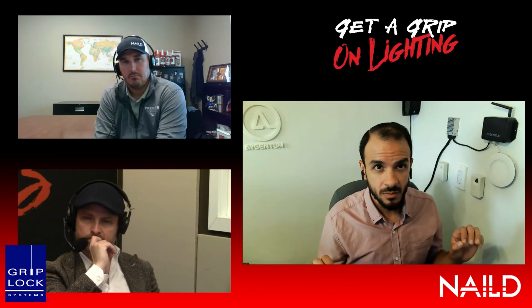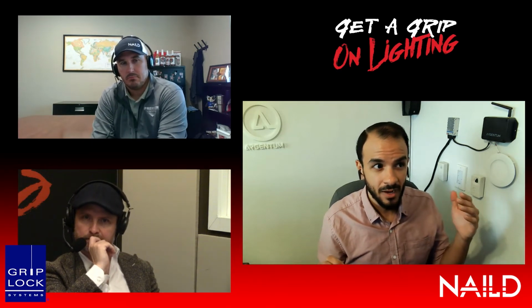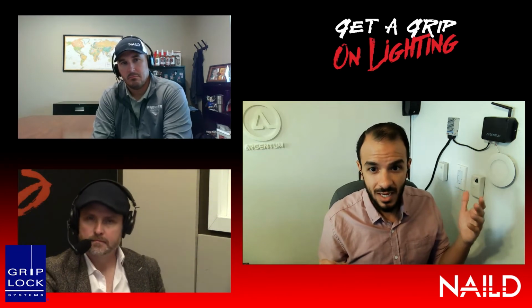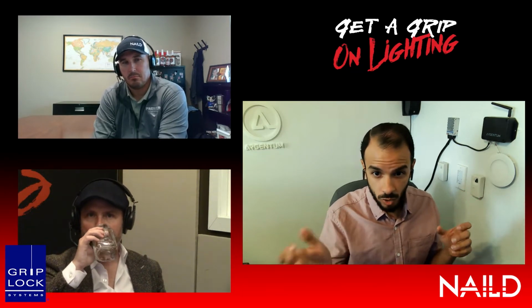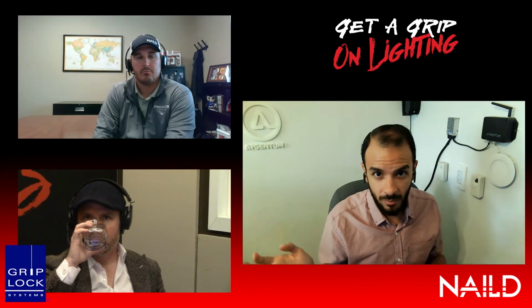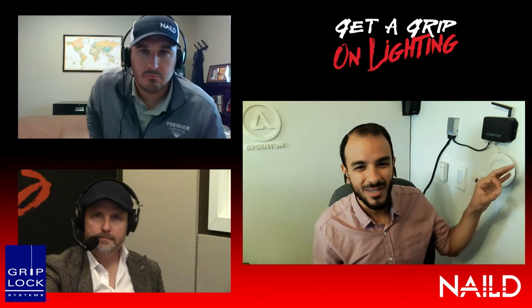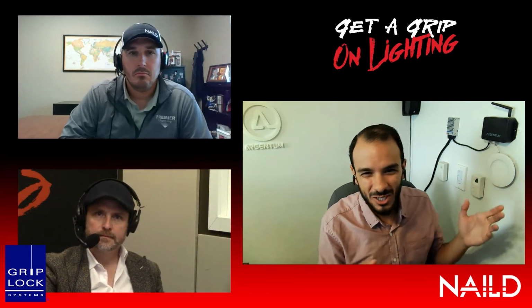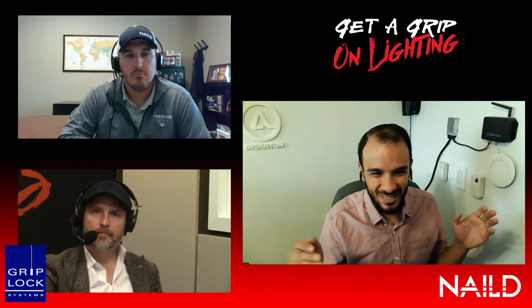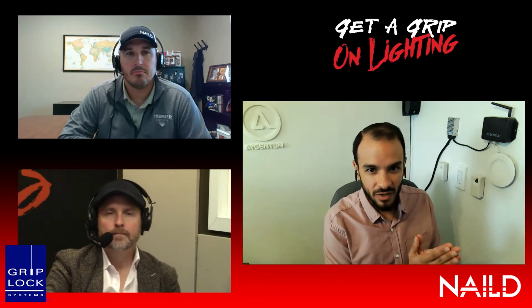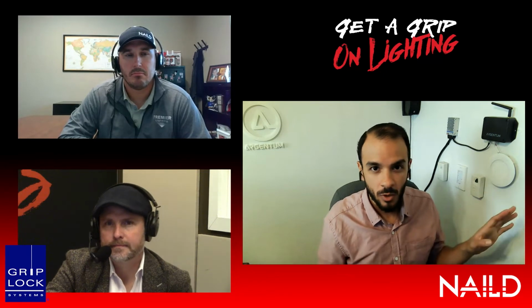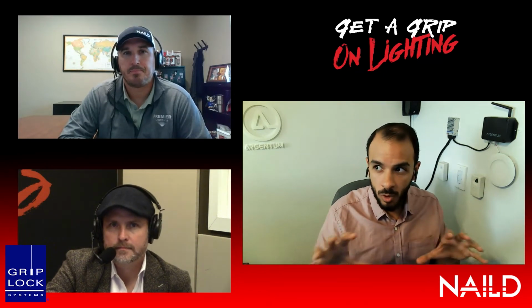The reason for this is we're at a point in time where sensor batteries last 10 years on a single battery. If you look at all of Lutron's sensors, it's all 10-year battery life — like Apple's AirTag, that's a 10-year battery. They don't even let you change the battery on some of these devices and sensors. So if we can get 10 years out of a wireless sensor, it makes way more sense to go wireless, because we can distribute more of them in locations where it's easy to install and easy to change the location.